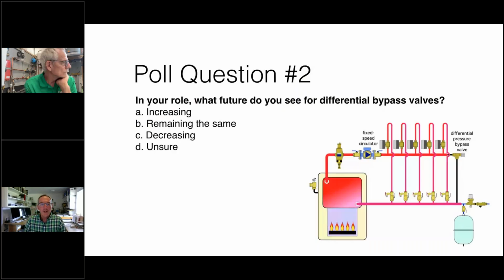Now, Max, let's run this poll. We talked about the differential pressure bypass valve, and we talked about it as kind of the classic way to control differential pressure in a zone valve system. But now with the new variable speed, pressure regulated circulators in the market, we're interested in your opinion. In your role, you may be an installer, an engineer, a wholesaler. What do you see as the future market for these differential pressure bypass valves? Do you think their use is going to go up, stay the same, decrease, or you're just not sure? We just want to get your thoughts on this valve as far as where you see it being used now and going forward.